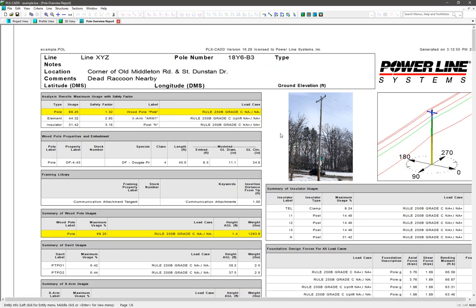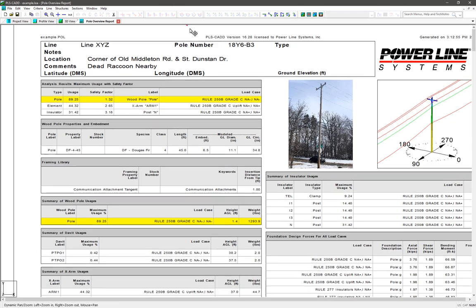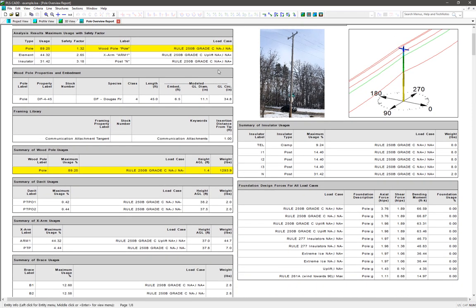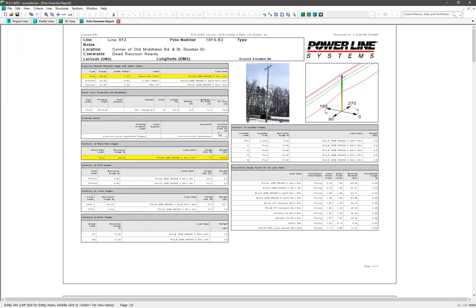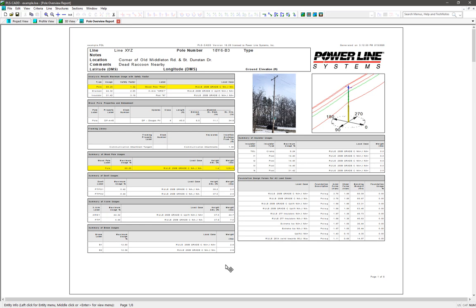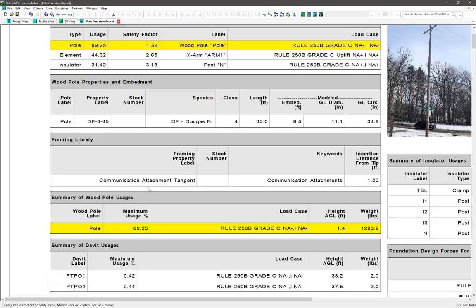Below that, we can see the usage and safety factor for the pole, the most utilized element, which in this case is a crossarm, and the most utilized insulator. Then below that, we can see more specific details for each entity of the structure, and also the foundation design forces at the ground line, and so on. All of these detailed sections can be configured before you generate an overview report. Notice how any element that's more than 75% utilized will be highlighted in yellow. And if there were any that were over 100%, then they would be highlighted in red.